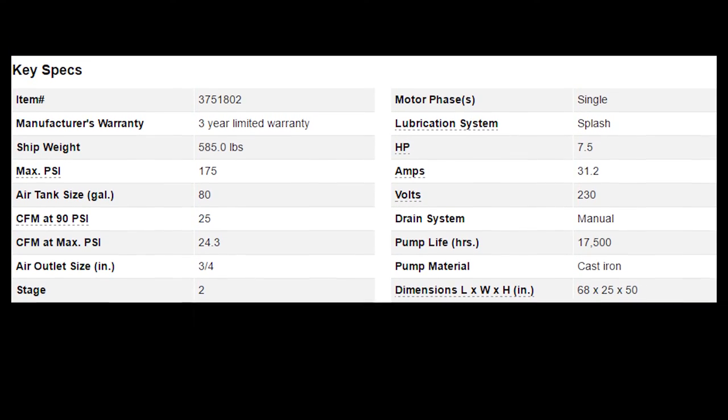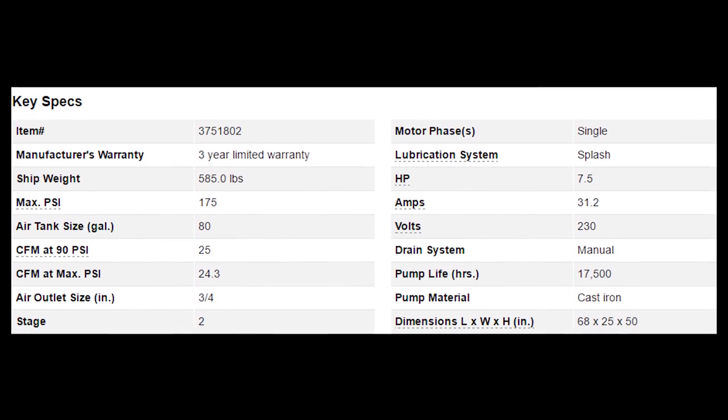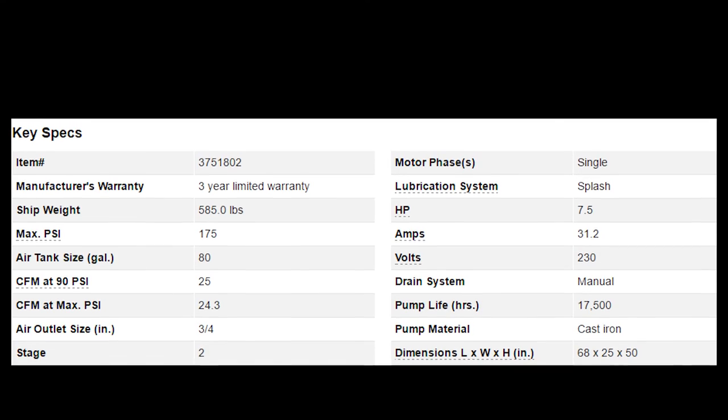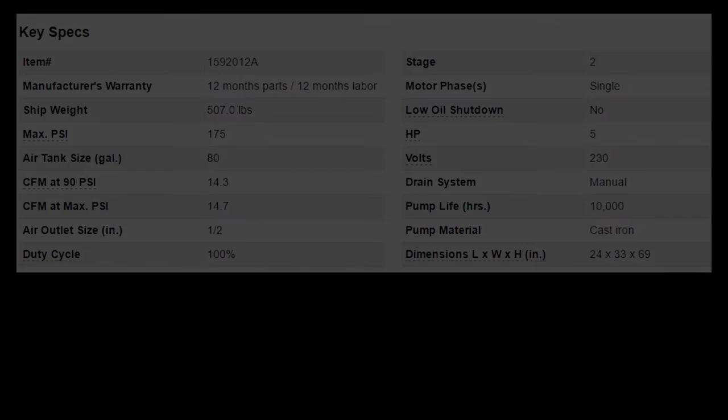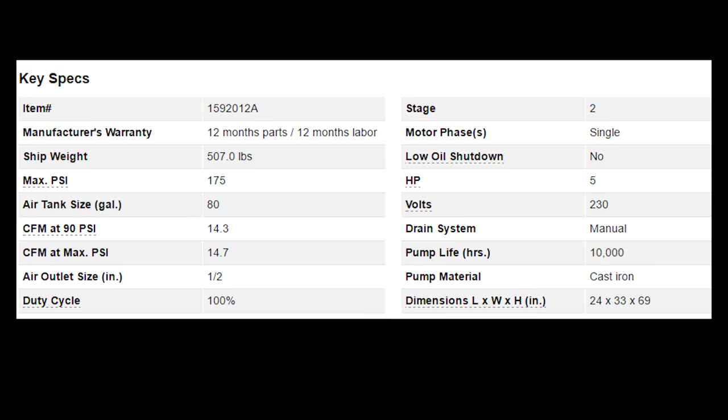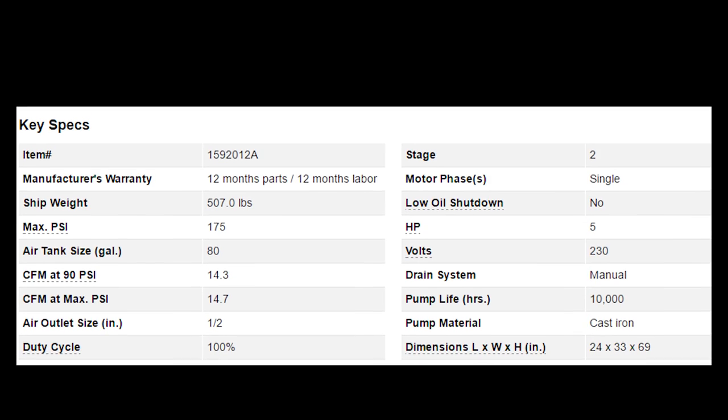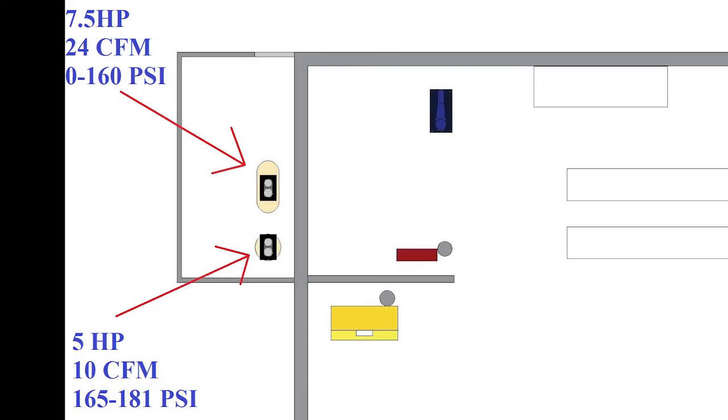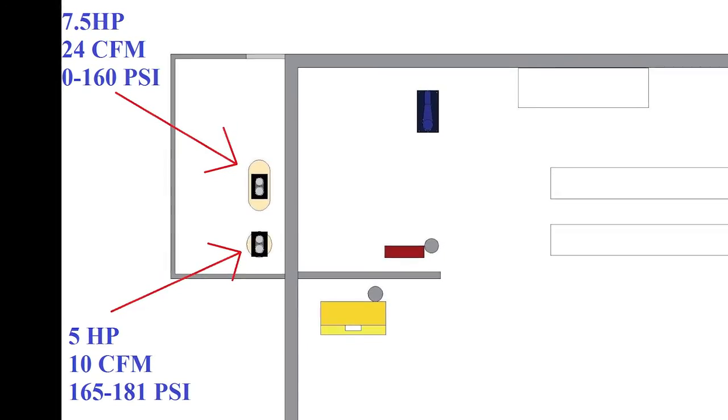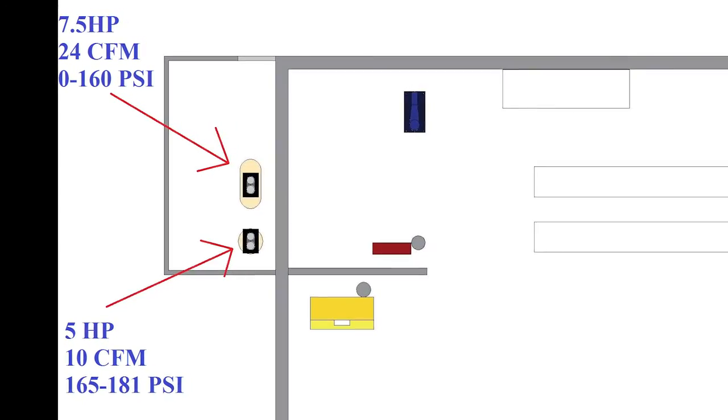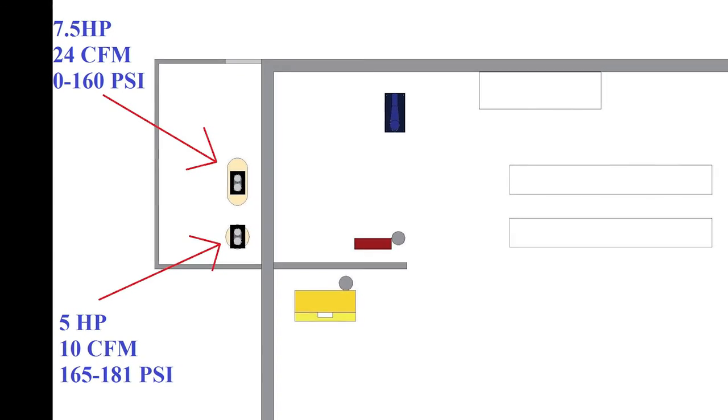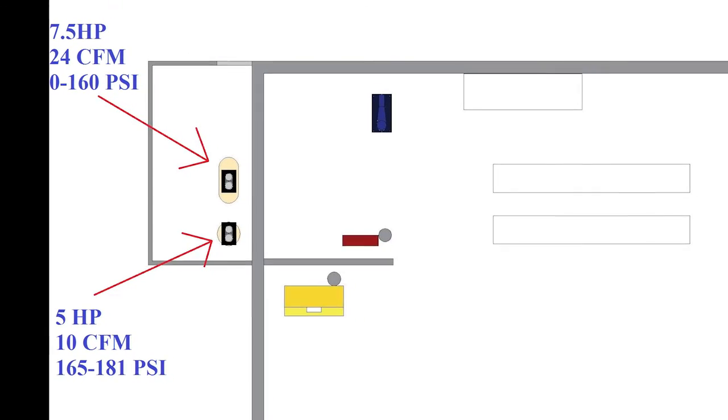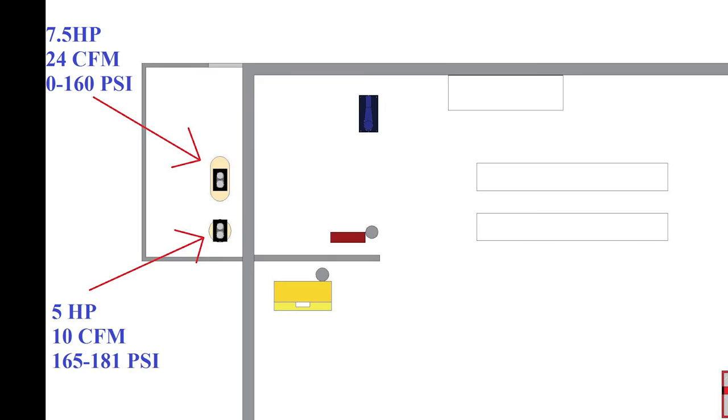To achieve this, we will use a 7.5 horsepower, 24 CFM free air compressor that will shut off at 160 PSI and a 5 horsepower compressor that makes 10 CFM when pushed to 180 PSI. In this top off and load configuration, the smaller 5 horsepower compressor will handle top off, starting at 165 PSI then off at 181 PSI.